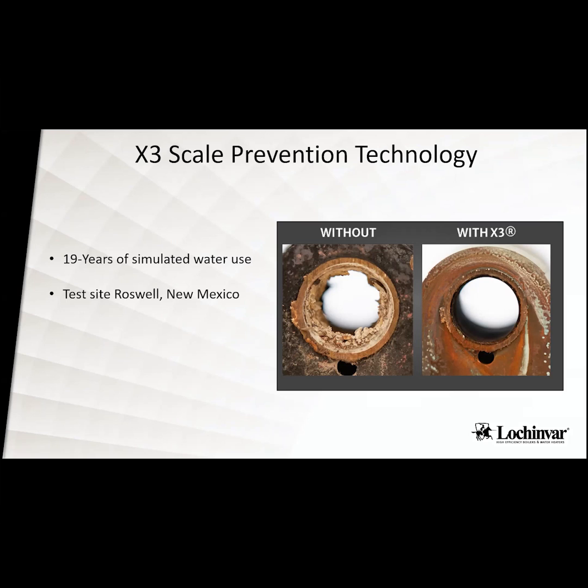So any questions on the filtration part of the unit? Yeah, Gail, this is Sean in Billings. Hey, is there a replacement interval on that scale cutter, or is it a non-consumable technology? It's a non-consumable technology. So it's like a salt-free softener. Yeah, so that cartridge will last the lifetime of that unit. So you do not need to change that out.